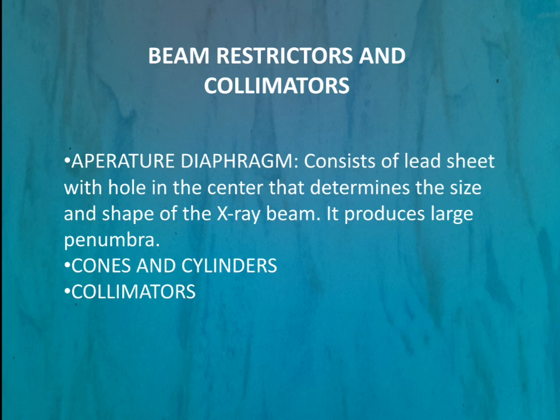The aperture diaphragm consists of a lead sheet with a hole in the center; this hole determines the size and shape of the x-ray beam. However, the aperture diaphragm has a disadvantage — it produces a large penumbra, causing unsharpness of the image. The size of the hole determines the size of the x-ray beam.